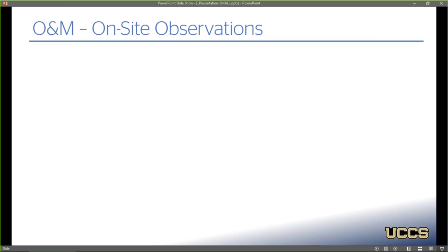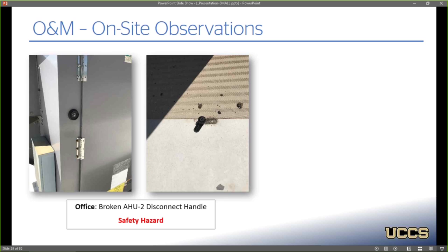So let's take a look at some observations I made on site. One of the rooftop units at the office building, the disconnect handle was broken and just sitting on the roof about 15 feet away, which isn't an energy concern, but it's a definite safety hazard. And so the customer was made aware of that immediately, and they did make a commitment to get it fixed.